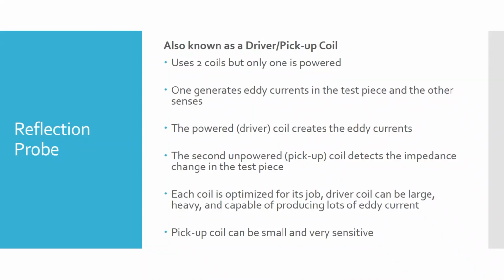What's nice is that with a single coil, or two coils that are both powered and both pick up, they may not be ideal for generating or detecting eddy currents—they're just okay at both. With a driver-pickup coil, a reflection probe, you can make your driver coil larger and able to put out a stronger magnetic field by running more power through it, while your pickup coil can be small and sensitive. So you put a lot more energy into the part and have a much more sensitive way of detecting changes in the signal coming back.